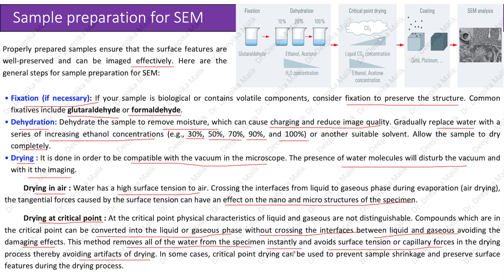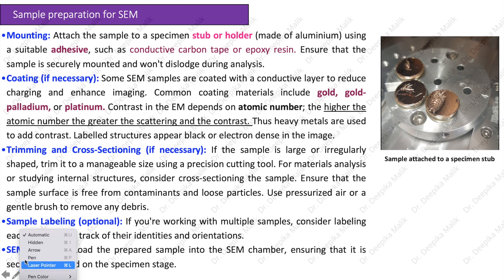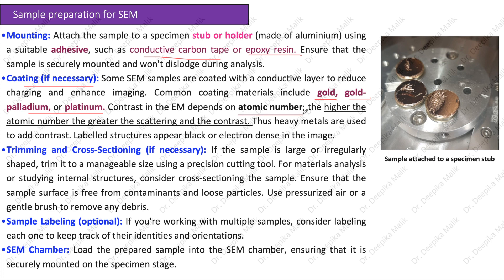Mounting: attach the sample to a specimen stub or holder made of aluminum using a suitable adhesive such as conductive carbon tape or epoxy resin, ensuring the sample is securely mounted. Coating, if necessary: some SEM samples are coated with a conductive layer to reduce charging and enhance imaging. Common coating materials include gold, gold-palladium, or platinum. Contrast in the electron microscope depends on atomic number — the higher the atomic number, the greater the scattering and contrast — so heavy metals are used to add contrast, and labeled structures appear black or electron-dense in the image.